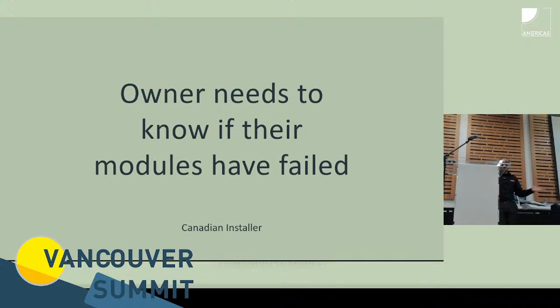So like, let's assume you've got 4 strings in parallel, okay? And you suspect that maybe one string is faulty. The string could have open-circuited, it could have short-circuited. If it's open-circuited, then basically you know that you've lost one string effectively. If it's short-circuited, when you've got them in parallel, you'll see a good portion of the parallel strings are sending their current on the bad string instead of into the inverter. So if you have a DC clamp meter and you see there is current in the opposite direction in this string versus what is going into the panels, then I know I've got a problem on this string.